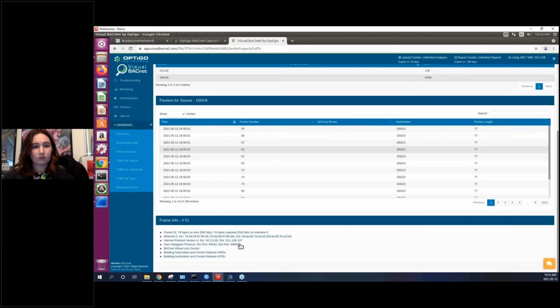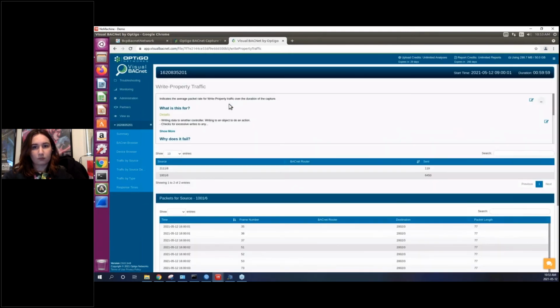And as we can see from our capture here, or our wiretap, our information is coming from the source of that JACE and being sent to our laptop. So we can see that our wiretap is indeed working, and we're capturing all that information on this side. We are able to then start building up that information from both our IP and our MSTP side, and ensuring that this is also, as we say, uncorrupted. Those wires, there's no extra impedance on the wires, there's nothing being added there. So we are getting as pure information as we can, better than we would be if we were putting something on that MSTP twisted pair.